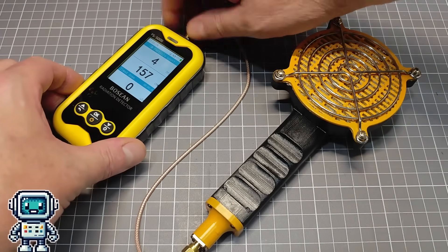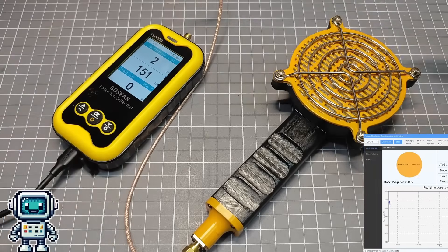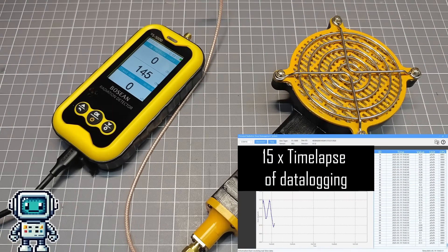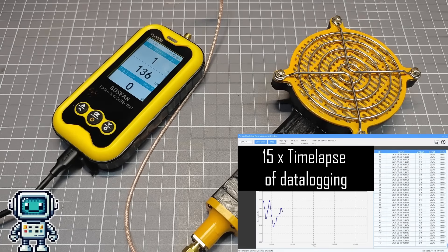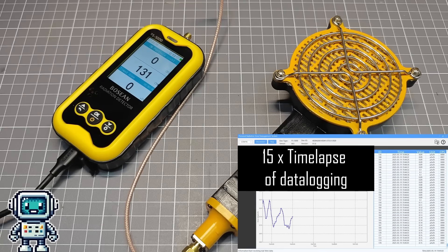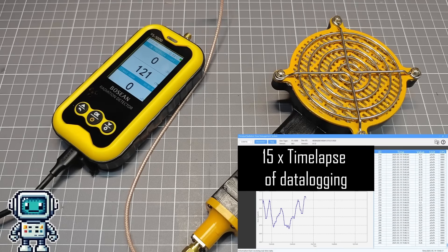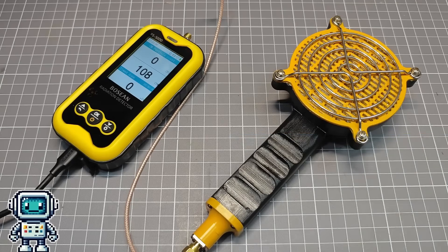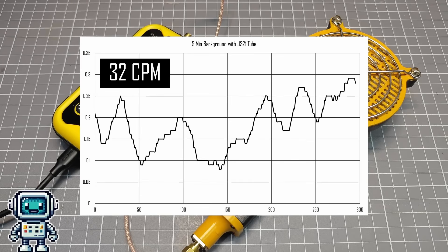First we are going to run a 5 minute test using the internal GM tube, it is always useful to have a baseline. Here in this apartment in Shenzhen China, we are expecting a dose rate of around 0.15 microsieverts per hour of background radiation. With the calibration that this device applies, that roughly translates to about 30 counts per minute. In the end, we get an average over 5 minutes of 32 counts per minute, so pretty close to the expected value. So far, so good.